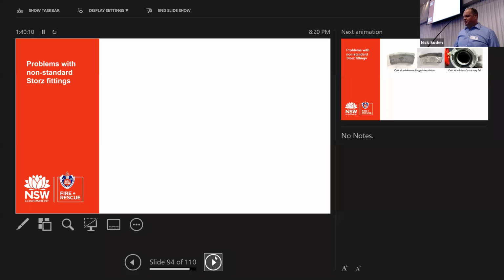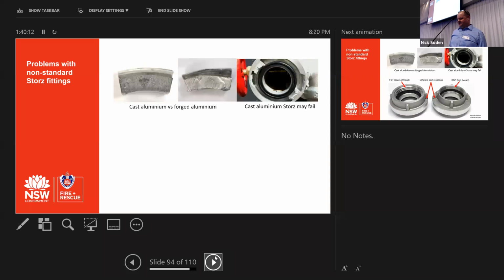Okay, so the problem with non-standard Storz fittings. You'll see here on an example, when you actually break the locking lug off, you can tell the difference between cast aluminium and forged aluminium. When you try and break off the locking lug of the cast aluminium Storz, it's very easy to snap off. It's so brittle, it has no strength in it whatsoever compared to forged.